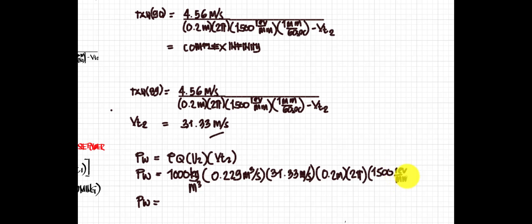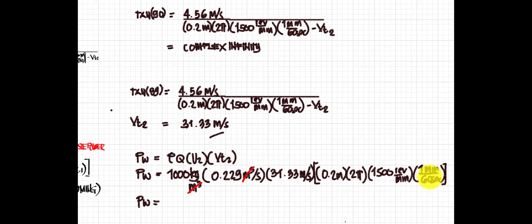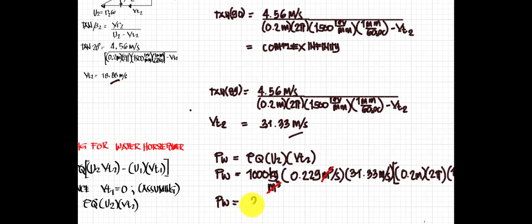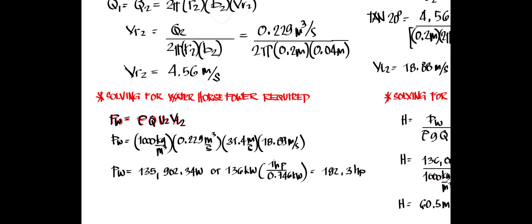For the value of u2, we multiply 0.2 m times 2π times 1500 RPM, then convert to seconds. Cancelling the units — kilogram, meter, second squared gives newton, then another meter and seconds — we get the output power equal to 225.39 kilowatts. This is the water horsepower required to produce that flow at 89 degrees, which is close to 90 degrees. At 20 degrees, the water horsepower was equal to 182.3 horsepower.